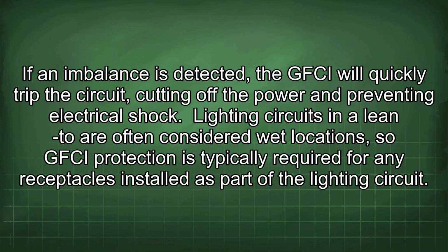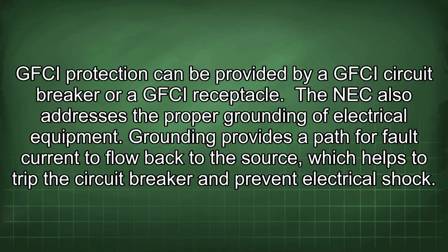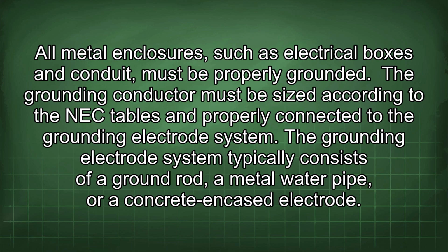Lighting circuits in a lean-to are often considered wet locations, so GFCI protection is typically required for any receptacles installed as part of the lighting circuit. GFCI protection can be provided by a GFCI circuit breaker or a GFCI receptacle. The NEC also addresses the proper grounding of electrical equipment. Grounding provides a path for fault current to flow back to the source, which helps to trip the circuit breaker and prevent electrical shock. All metal enclosures, such as electrical boxes and conduit, must be properly grounded.